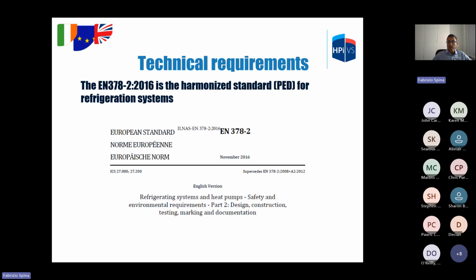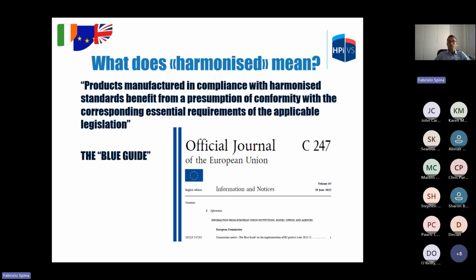Now we can move on to the technical requirements and discuss how to meet the PED obligation from a technical perspective. For refrigeration systems requiring CE certification, the reference standard is the EN378 Part 2. That is what we call a harmonized standard. But what does harmonized mean? The definition of harmonized is set out in the Blue Guide. The Blue Guide provides guidance and explanation on the European conformity assessment system, on the CE marking, and the market surveillance. It includes general definitions such as manufacturer or placing on the market.